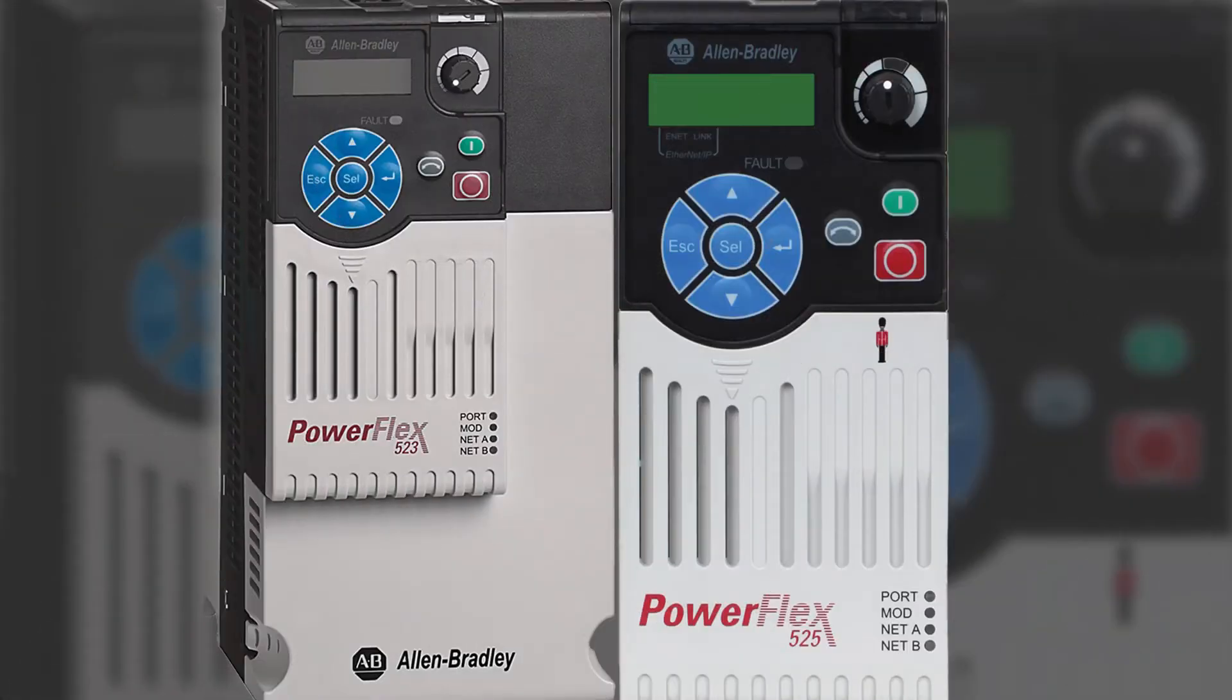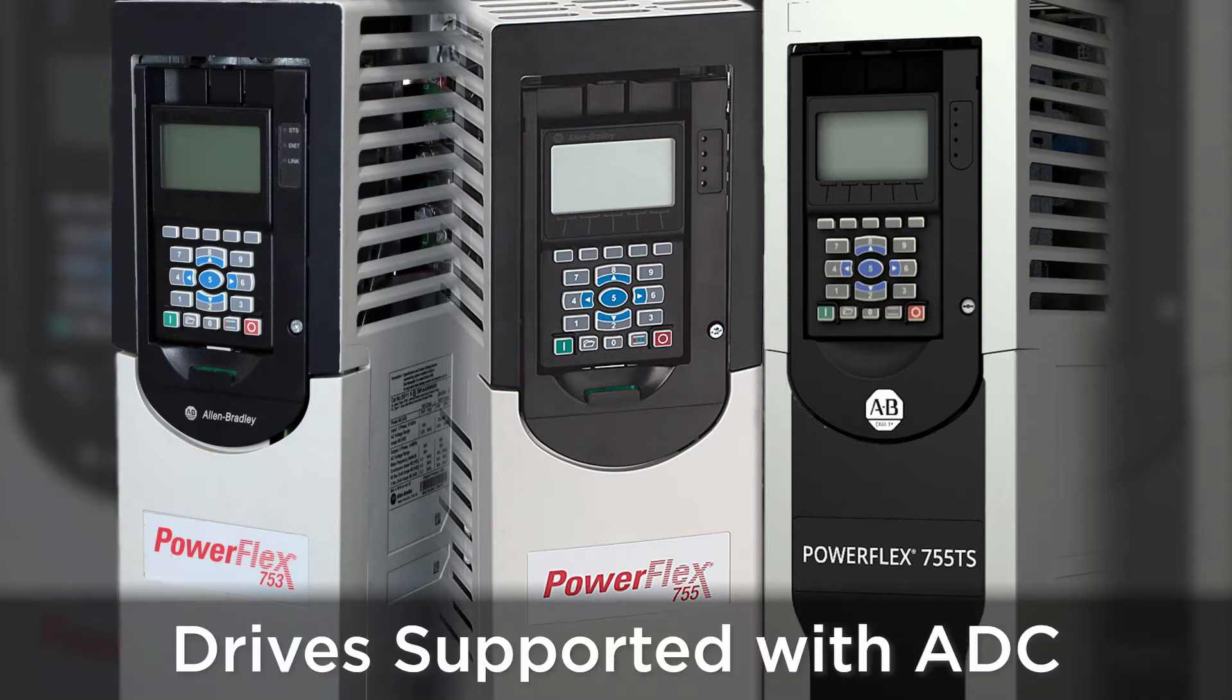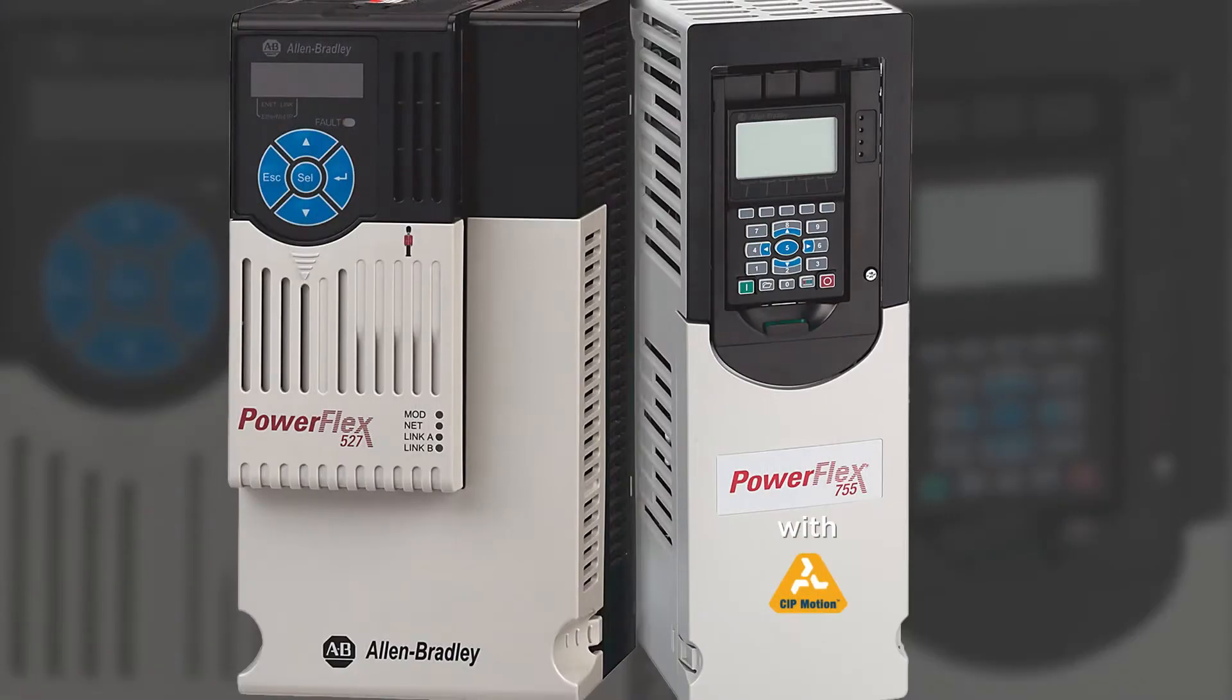Currently, PowerFlex 523, 525, 753, 755, and the 755TS drives are supported with ADC. If the drives are set up for motion, such as 527 or 755 with CIP Motion, then ADC is not necessary because the parameters are configured within the motion axis that controls the drive.